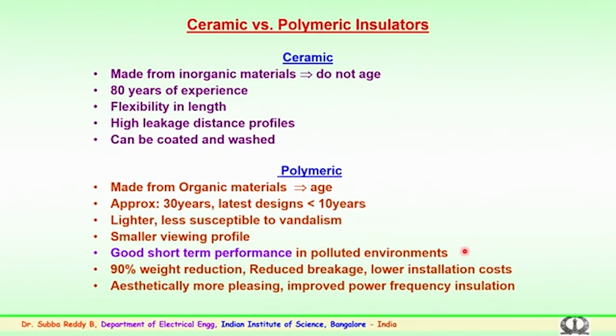They will be very happy to have better performance of the insulator strings in polluted environments. And there is a reduction in weight; again it depends on the voltage level where a comparison could be made, and most of the time the weight reduction is anywhere between 90% and also reduced breakage, lower installation cost compared to the ceramic insulators, and aesthetically they are more pleasing, look much better, and also have better improved power frequency insulation levels.